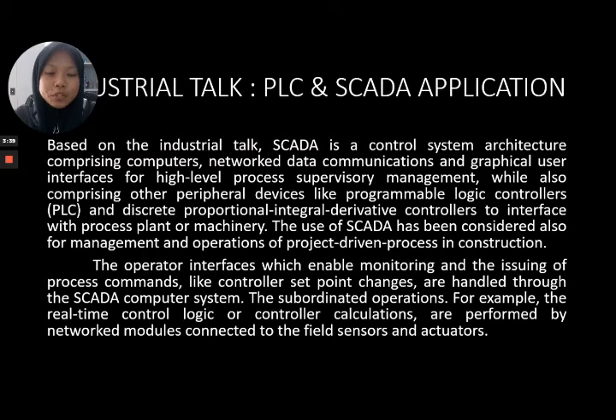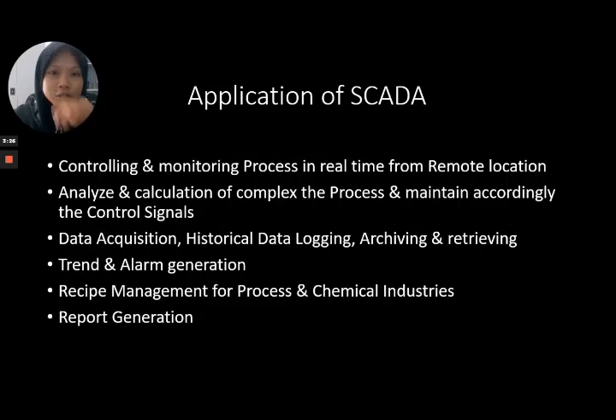The subordinate operations, for example, the real-time logic control or controller calculations, are performed by network modules connected to the field sensors and actuators. Okay, this is an example of the application of SCADA: controlling and monitoring processes in real time from a remote location. Furthermore, analysis and calculation of complex processes and maintaining the control signal accordingly. Moreover, data acquisition, historical data logging, archiving and retrieving. In addition, trend and alarm generation and recipe management for process and chemical industry. And last but not least, report generation.